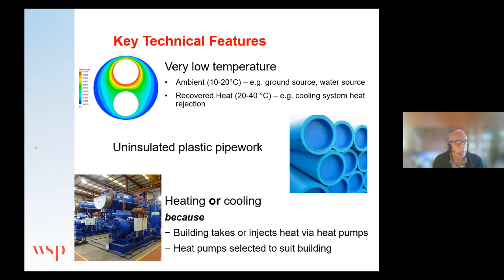Because those systems are of such low temperature, you could be using uninsulated plastic pipework - the sort of MDPE pipework pictured there on the right. You can do this at quite large scale, thinking about big water or gas pipes in the ground. It's quite a lot cheaper to install, and also easier to handle than the standard pre-insulated steel pipework you'd normally look at in district energy.